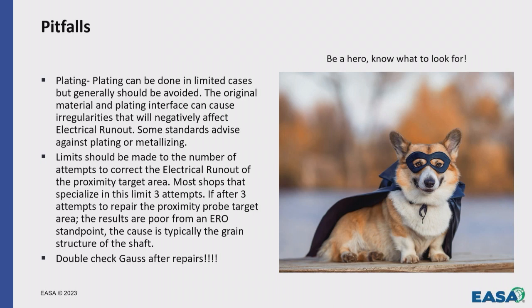And then limits. So the other piece on the initial motor I mentioned was the attempts to correct electrical runout. So if your electrical runout's high and your Gauss is good, there's a couple things that still affect it, and one of those is the grain structure of the material you've got. So particularly in machines that did not come with proximity probes, the grain structure of the shaft, if it's a lesser expensive material or there's a flaw anywhere in the shaft, there may not be anything you can do to fix that electrical runout. And that's what we ran into with this particular machine.